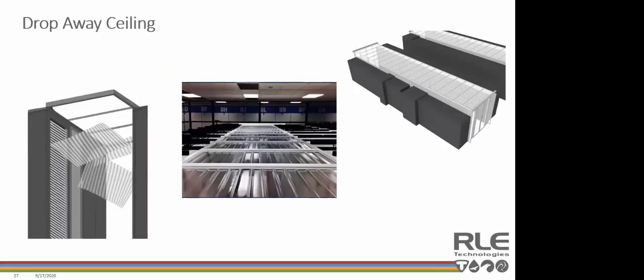One way to make sure that your plenum is going to be open to fire suppression systems if an event should occur is to use drop-away ceiling panels. We recommend these a lot. These can be used in conjunction with soft containment solutions as well, not just rigid. The drop-away ceiling panels are made from a lightweight, clear, translucent plastic material that has a very specific shrinking point or melting point. Our panels happen to activate at 165 degrees Fahrenheit. Should there be a fire event and that temperature is reached, the panels will shrink and drop out of their aluminum frame and fall harmlessly to the floor. This opens up the contained space to the existing fire suppression systems in a data center room.